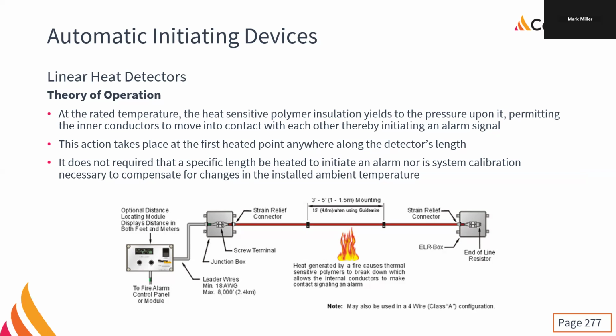I haven't installed one of those yet. But if you're trying to protect something very, very long, like a conveyor system, and you want to know if there's a fire condition exactly where it is, you can use a distance locating module, and it can tell the distance based on the resistance once it activates, because that wire has a known resistance, and it'll give you the distance in feet and meters.